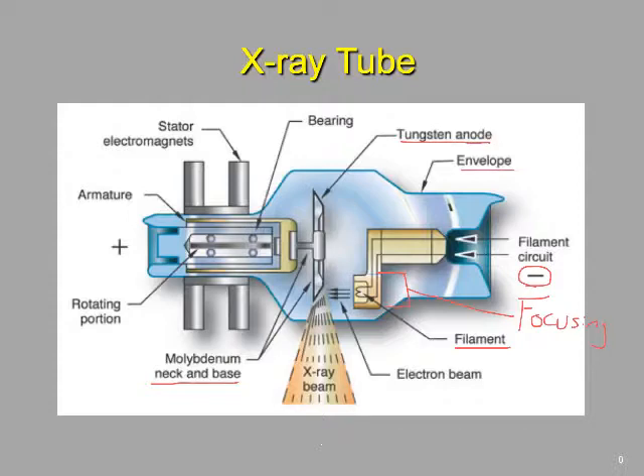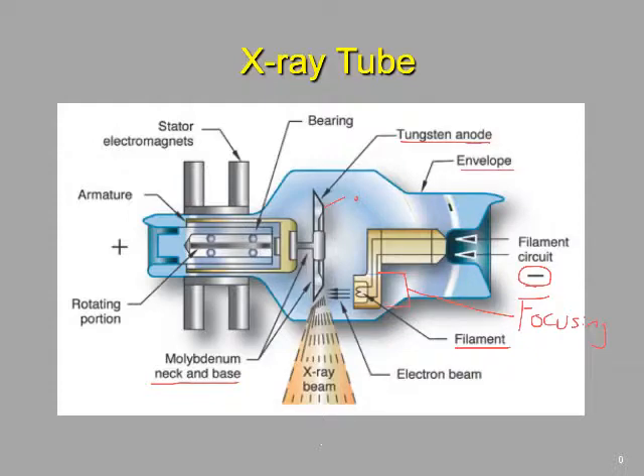If an electron strayed out before we energized the anode, it might hit somewhere else on the anode and produce what we call off-focus radiation. We want that focusing cup to be negatively charged to push the electrons back toward the filament. When we energize the anode with a kilovoltage of potential energy, the electrons are going to jump and be accelerated close to the speed of light across roughly an inch of space.